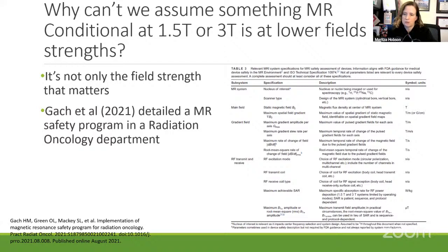So recently, Gach et al. detailed an MR safety program in their department, including how they cleared devices for their 0.35 Tesla MR Linac system. They put their safety protocols, procedures, and documents in place for this situation. And I did something similar for the MR-guided radiotherapy system that I worked at previously. This is one of our recommendations in TG334. With the lower field strength MR Linac having to perform these extra steps of clearance of a device, either internal or external, will occur quite frequently. So it is imperative to have a documented departmental process with the parameters as listed in Table 3 for your system, so that it's easy to determine if the device is MR conditional in your MR system. I did that for our system, and it helps out. Then it's also useful if you go on vacation, because someone else who has been trained properly can also do that.